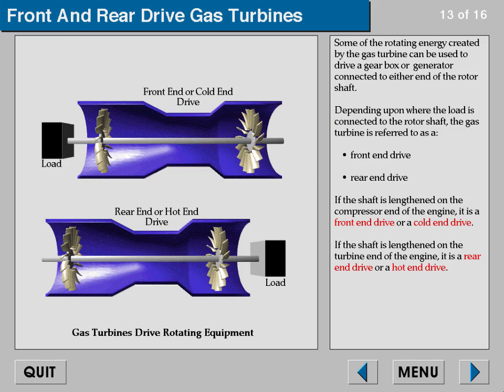Some of the rotating energy created by the gas turbine can be used to drive a gearbox or generator connected to either end of the rotor shaft. The gas turbine is referred to as a front end drive or rear end drive. If the shaft is lengthened on the compressor end of the engine it is a front end drive or cold end drive. If the shaft is lengthened on the turbine end it is a rear end drive or hot end drive.